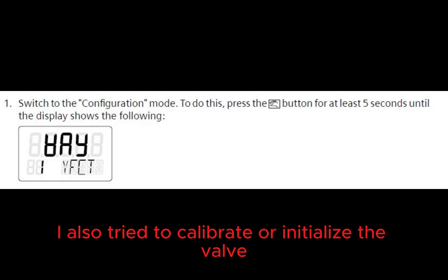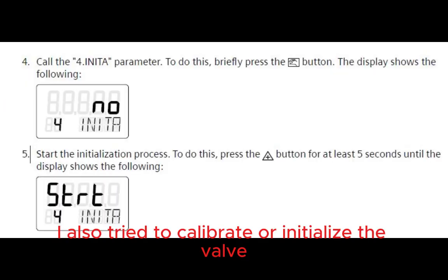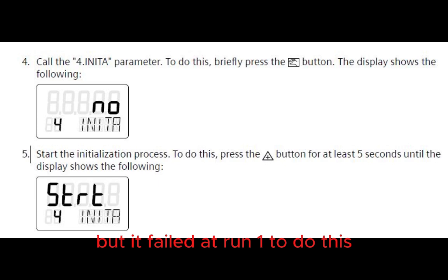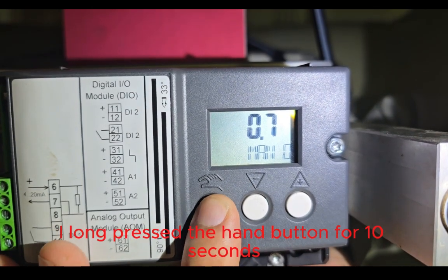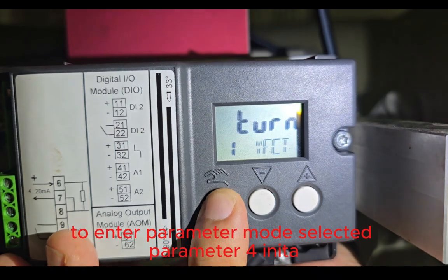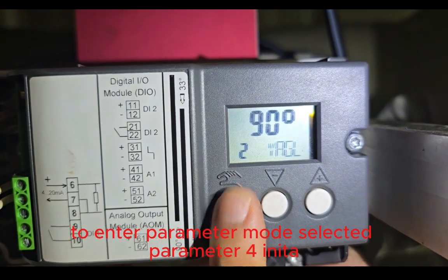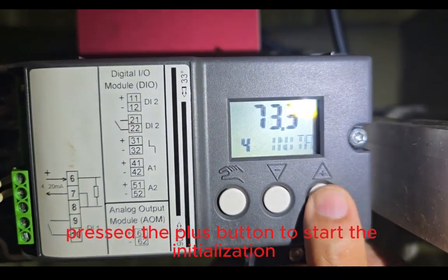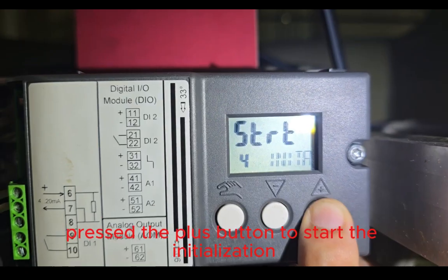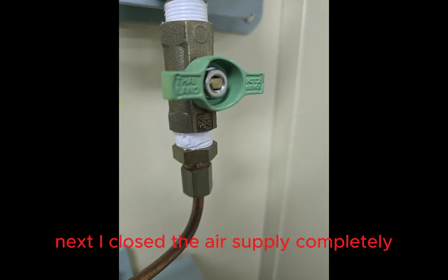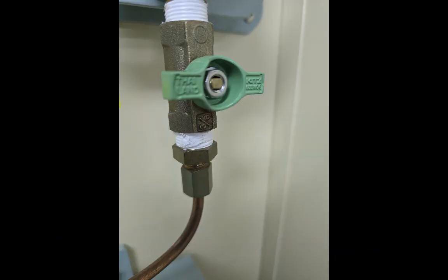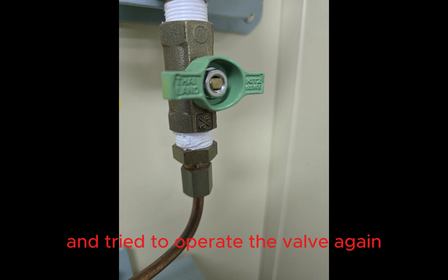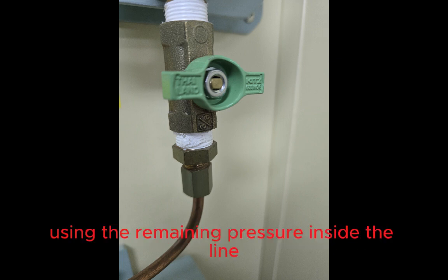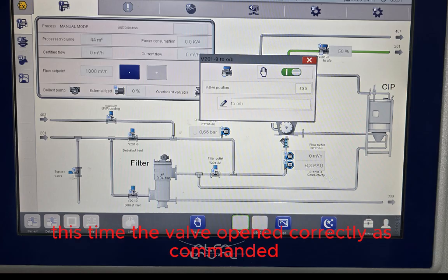I also tried to calibrate or initialize the valve, but it failed at run 1. To do this, I long pressed the hand button for 10 seconds to enter parameter mode, selected parameter 4 in ETA, then long pressed the plus button to start the initialization. Next, I closed the air supply completely and tried to operate the valve again, using the remaining pressure inside the line. This time, the valve opened correctly as commanded.